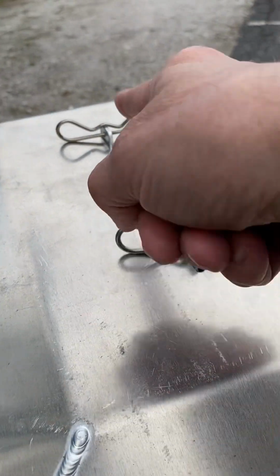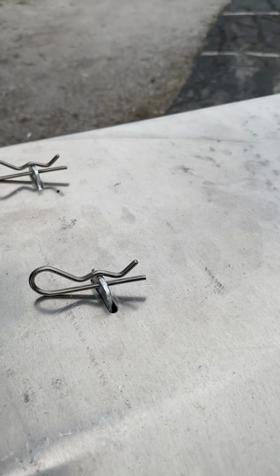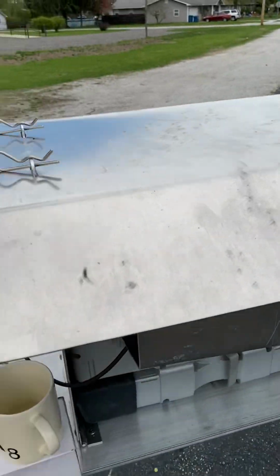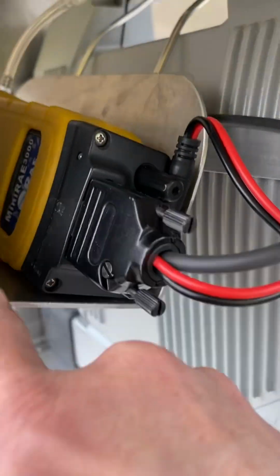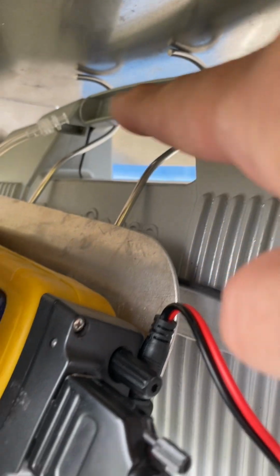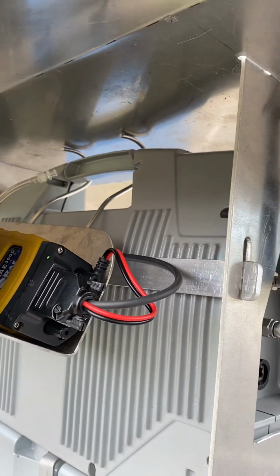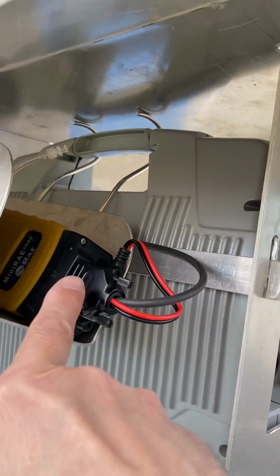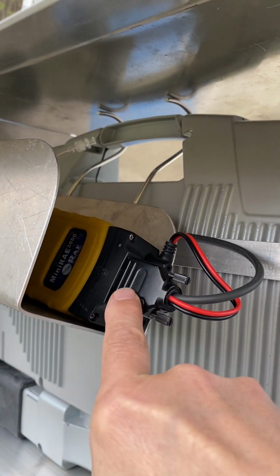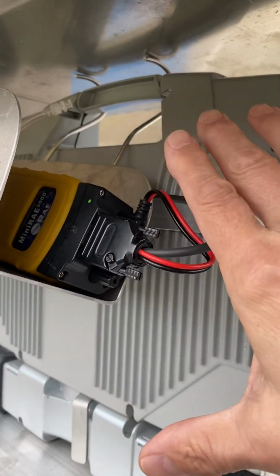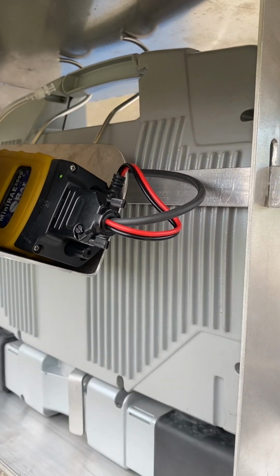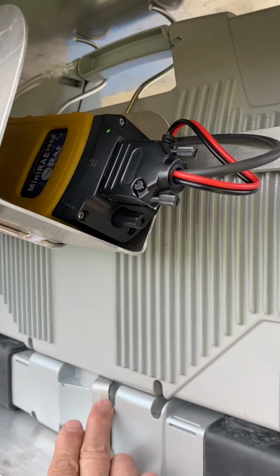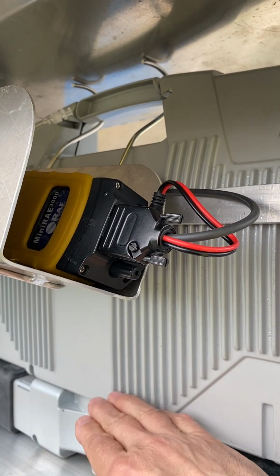Coming back around here at the top, you're going to see cotter pins. This is how the quick releases work to take this whole quad pod down. Very simple and easy. And again, I told you 5 minutes to put together and 5 minutes to take down. You'll see this tray for third-party devices has little hooks that go on the handle and fit easily underneath the rain shield there. And our interface is just this electronic connection right here for this MiniRAE. Now, not only is it sending communication and data, it's also using the power from the AccuSense to power up the MiniRAE 3000. So that's kind of cool. And again, here's a release lever to separate the 2 halves, the 2 different battery halves.